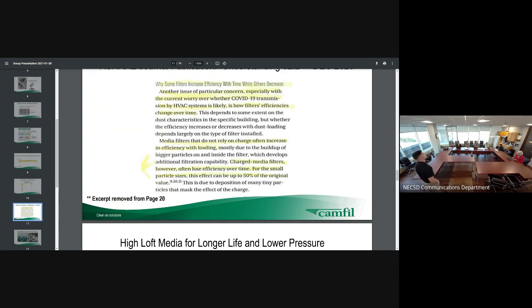So, what I get out of this is, your filters are cheaper in the yearly run of things. Yes. Your filters do not filter out viruses. They do not. The other filters do for a much shorter period than we think they do, but they do it for part of their lifespan. Unfortunately, we don't have an exact metric for how long synthetic charges last. It depends on the nature of the HVAC system, their handling, their age. Some MERV 13 filters that you're buying are already not a MERV 13 because they've been touched too much and the charge has been dissipated.